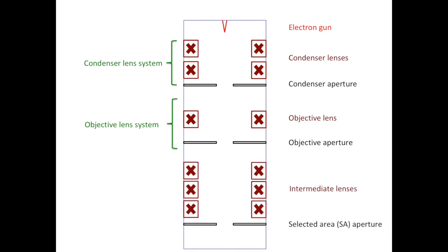Finally, we have the intermediate lenses and the selected area aperture or the SA aperture. They make up the projector lens system. By changing the strength of the intermediate lenses, you can either change the magnification of your image or change the camera length of the diffraction pattern.